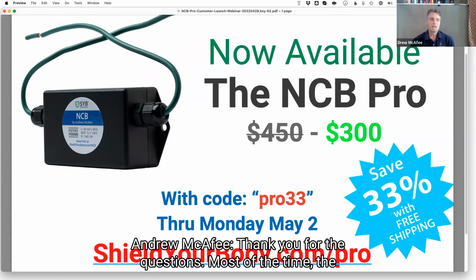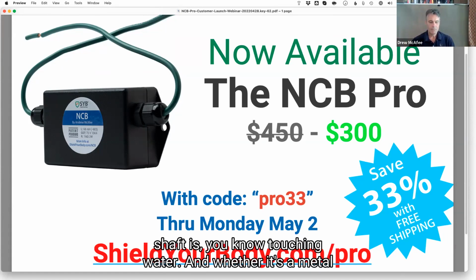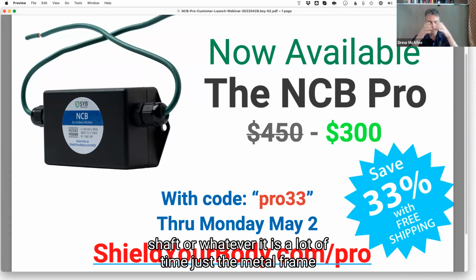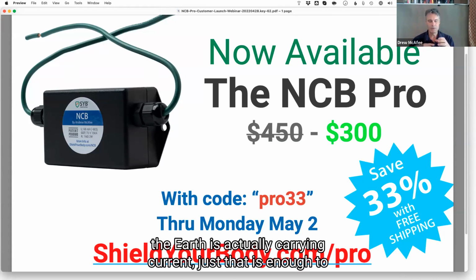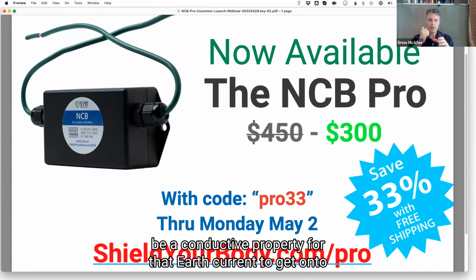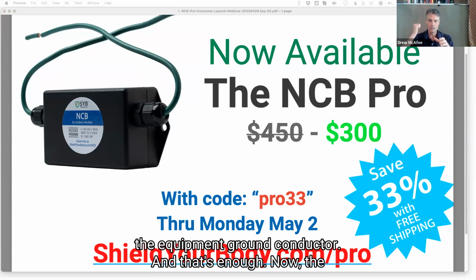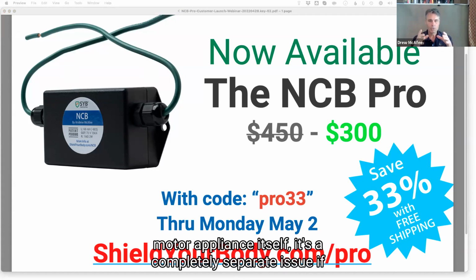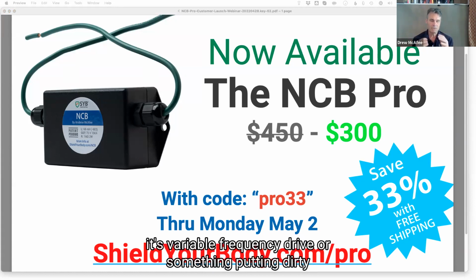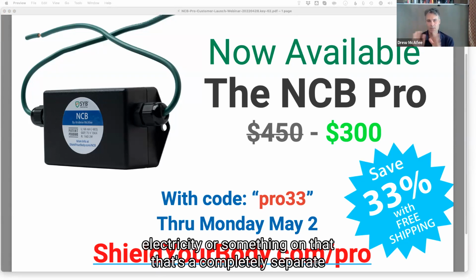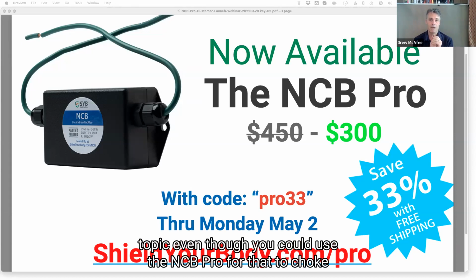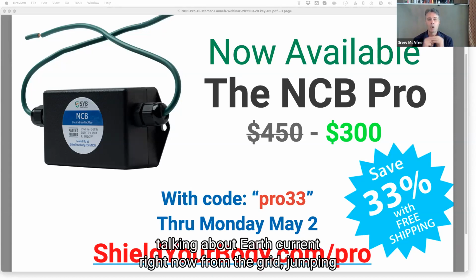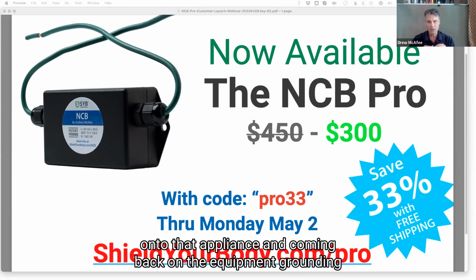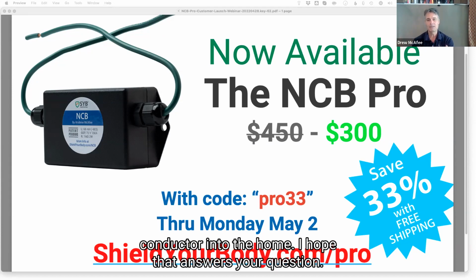Thank you for the question. Most of the time the shaft is touching water, and whether it's a metal shaft or the metal frame housing that's connecting to the earth, the earth is actually carrying current. That's enough of a conductive property for that earth current to get onto the equipment grounding conductor. Now the motor appliance itself is a separate issue. If it's a variable frequency drive putting dirty electricity on that, that's a separate topic, though you could use the NCB Pro to choke those frequencies on the grounding conductor. But we're just talking about earth current right now, from the grid jumping onto that appliance and coming back on the equipment grounding conductor into the home. I hope that answers your question.